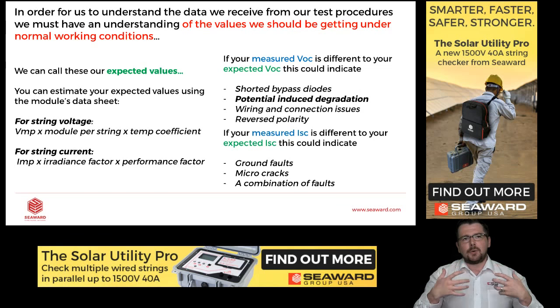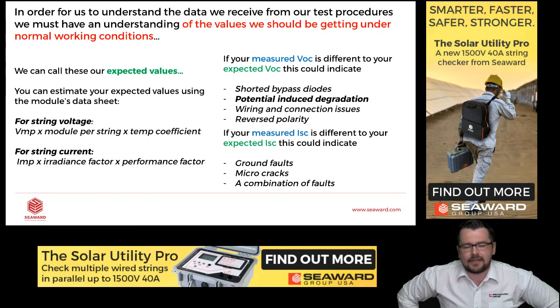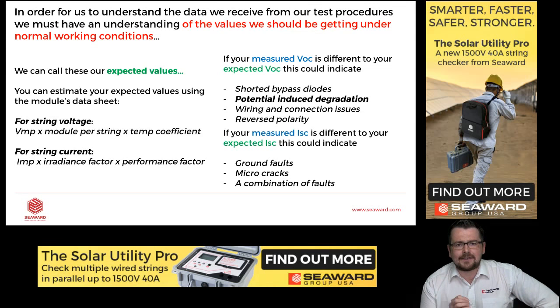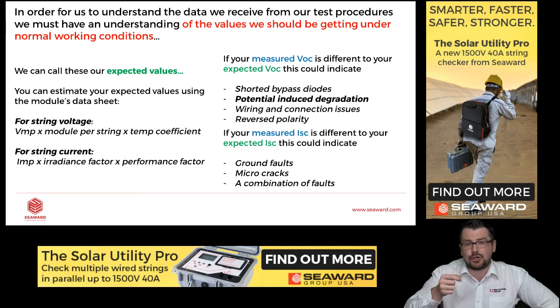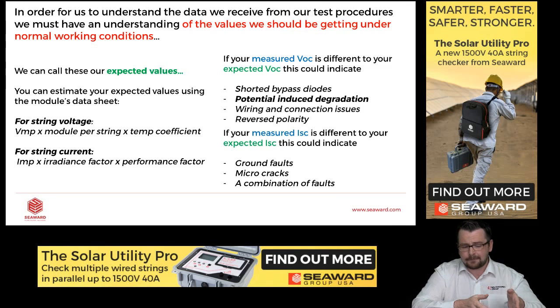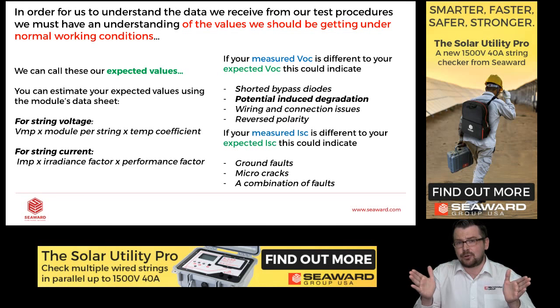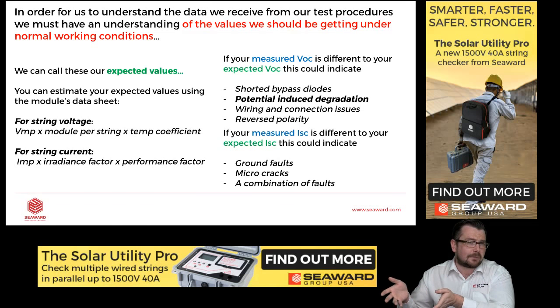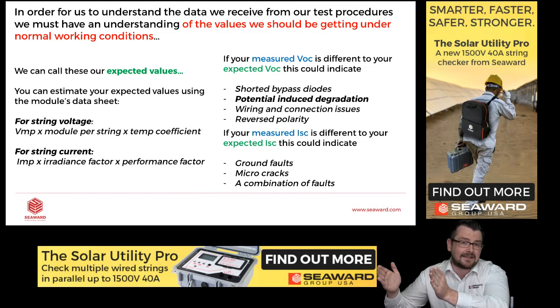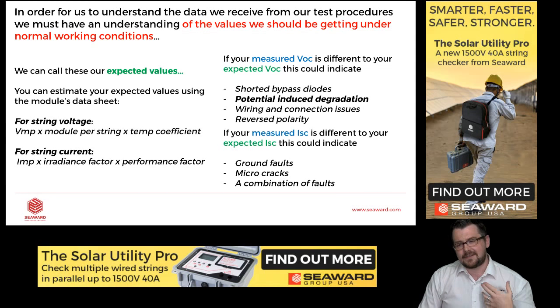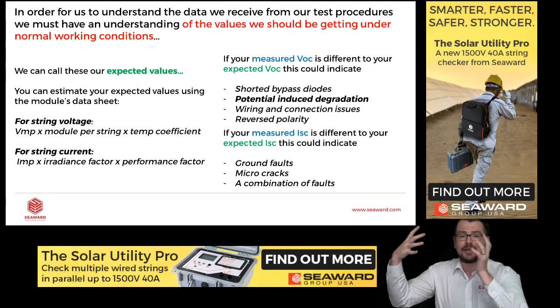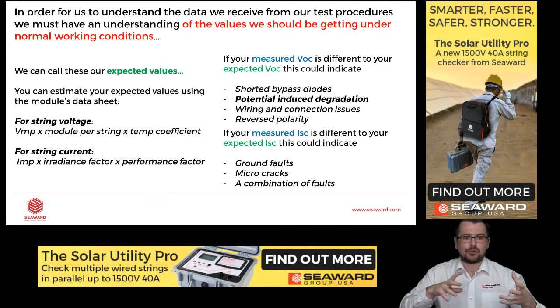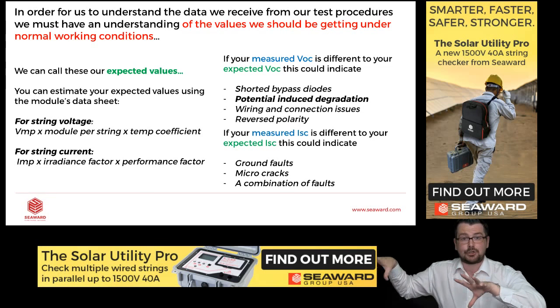So, as well as all of this pre-testing preparation we've already done, I mentioned that we should understand what kind of voltages and current ratings we are going to get from the system that we're going to test. And we can do this very easily using some simple maths. So for instance, for our string voltage, we can calculate what we should expect by taking the number of modules in the string and the STC VOC, and multiplying those two together. We can also multiply by the temperature coefficient, but this will give us what our expected open circuit voltage should be. So for instance, if each panel is 40 volts, we have 10 panels, we should have 400 volts, okay? And this is also affected by temperature, so we should also multiply by the temperature coefficient.